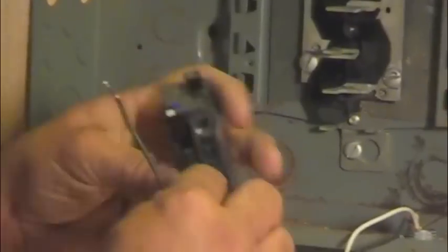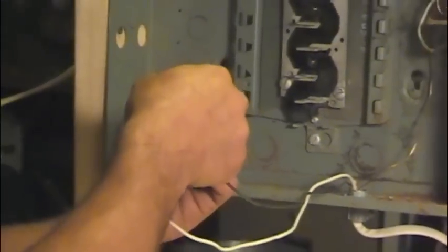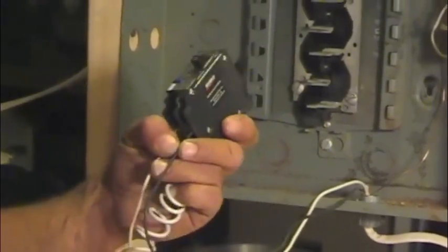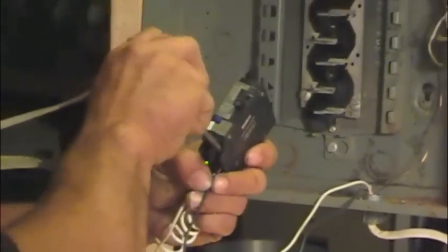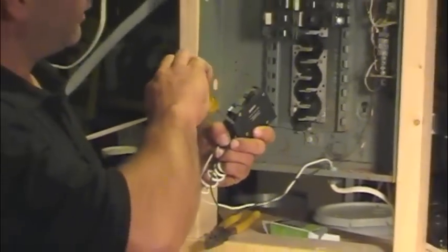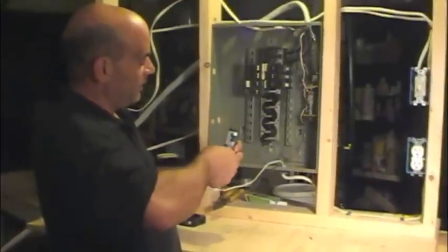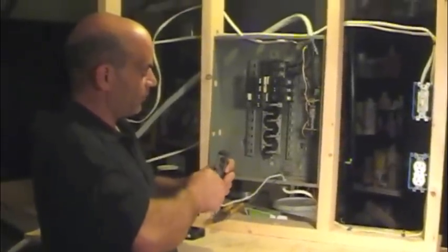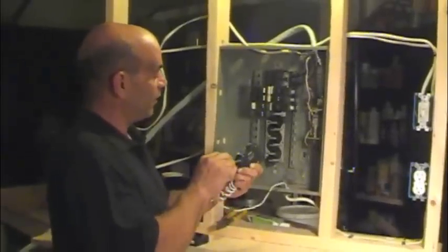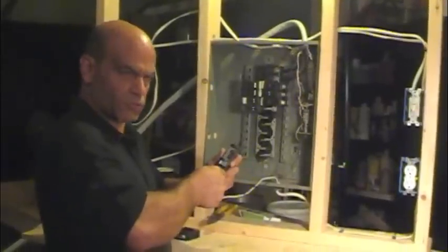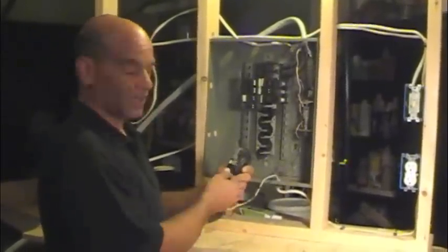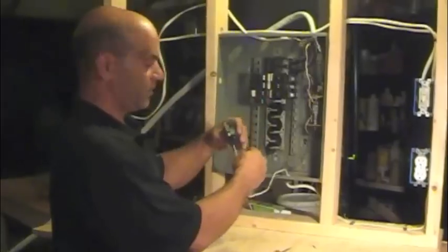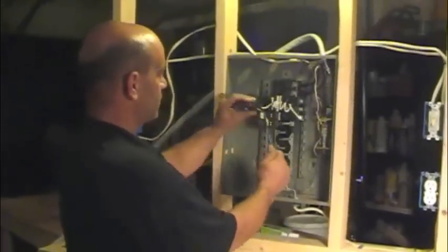Again, I already know that this terminal here is where our hot lead goes. I'm going to tighten that up while I'm holding that in. Again, when you're tightening these, this breaker is plastic and they're built pretty good, but if you start tightening that screw way too much, you have a good chance of breaking that. So tight, snug without breaking it.